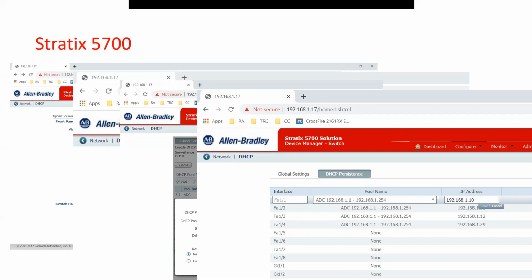I get a lot of comments, people saying, I don't want to use a managed switch because I don't know how to configure it or set it up. I actually had a salesman say I don't like selling them because my customers are intimidated by them. I'm going, can your customer land a plus wire on the plus terminal and a negative wire on the negative terminal and give it proper 24 volts? He goes, yes. I go, then he's just configured the managed switch. Out of the box, powered up, these switches will work. They'll communicate, and you really don't have to do a thing. You want to, but you don't have to.